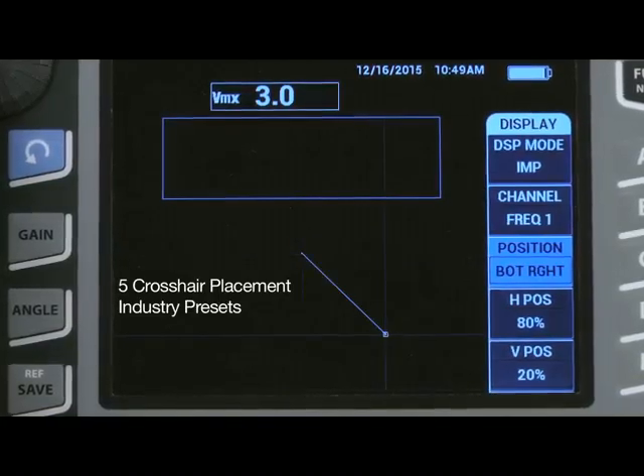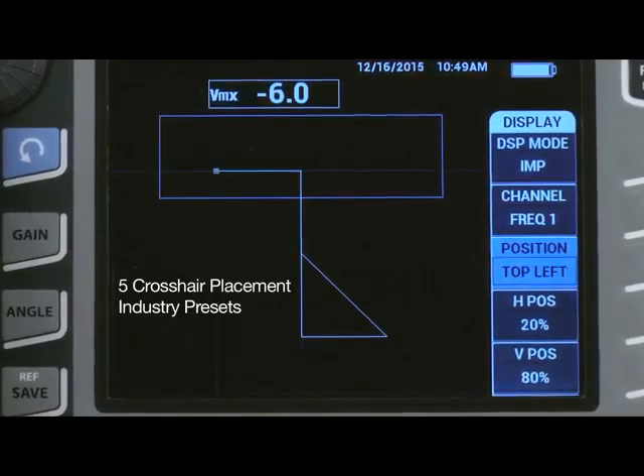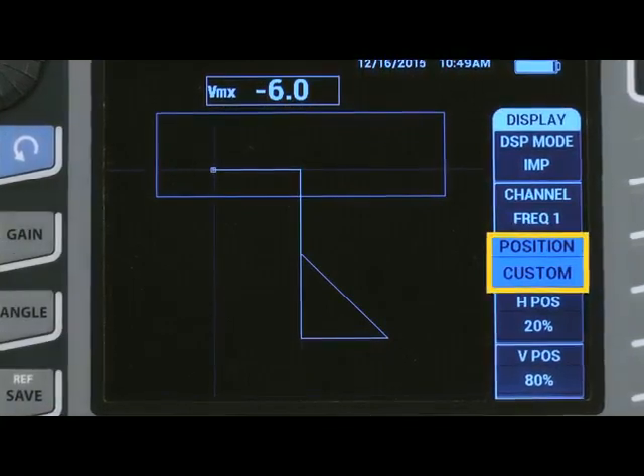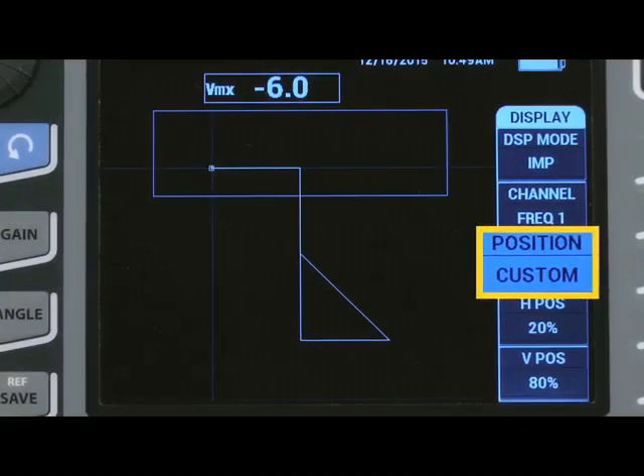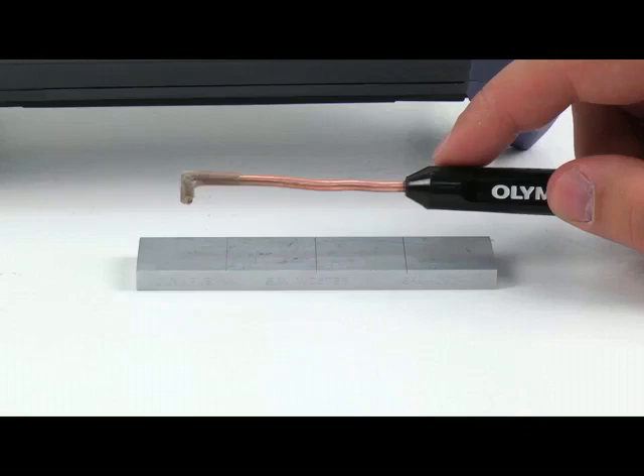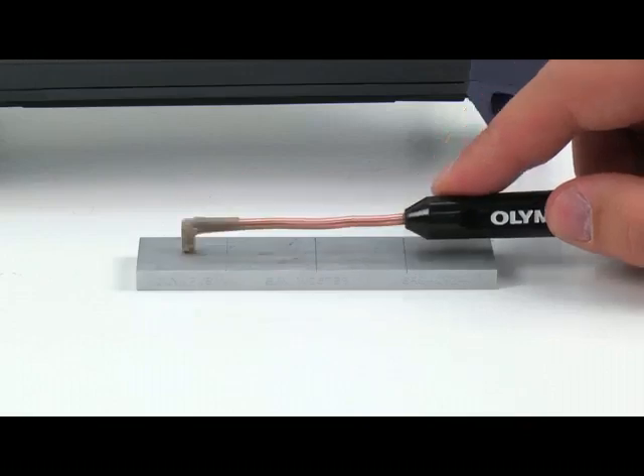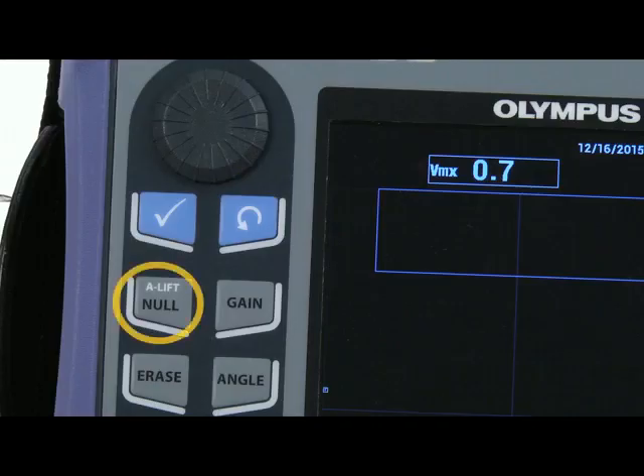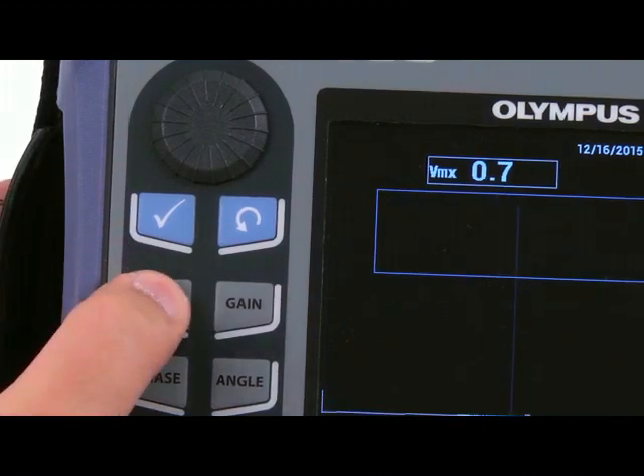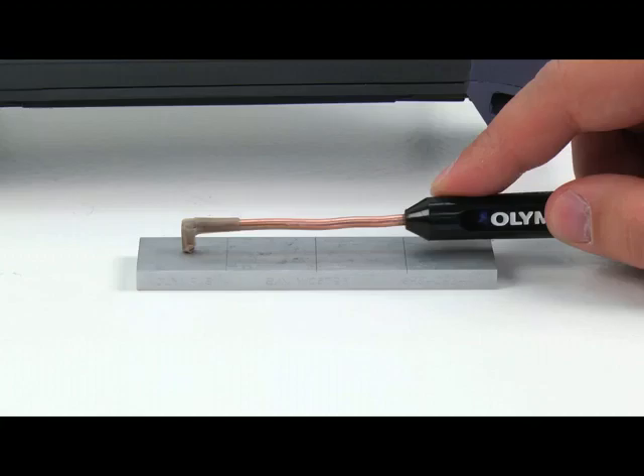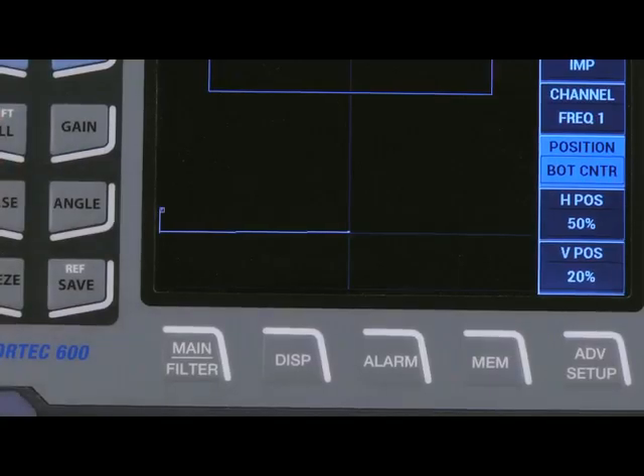There are 5 commonly used industry presets to facilitate the placement of the crosshair. A 6th preset is available for user customization. Place the probe on a defect-free area of the standard. Press and hold the null key. This will activate the auto liftoff function. When you hear the beep, lift the probe. The cursor should appear on the horizontal axis to the far left. If it does not, repeat the step.